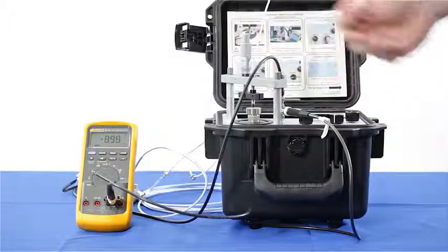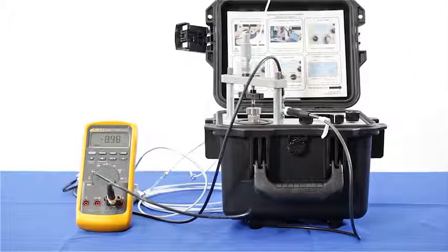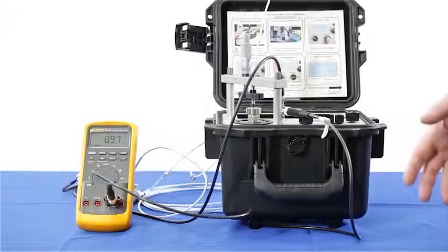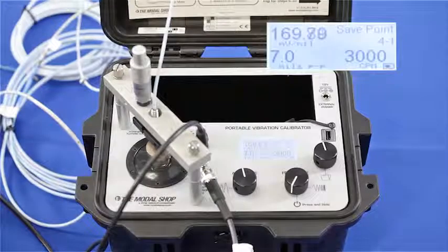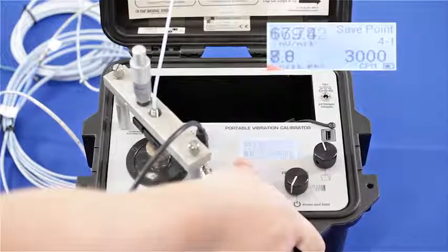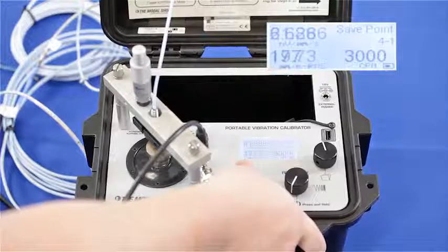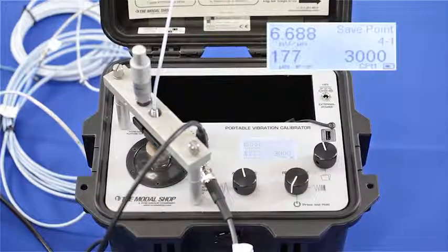So I can make my gap voltage look correct at -9 volts by moving the proximity probe, in this case, a little bit further away from the target. And that's going to cause our dynamic output to change even more. You can see now that I've corrected my gap voltage and mistakenly changed the position of the proximity probe, my output has dropped even further to 177 millivolts per mil, or in microns, an output of 6.68 millivolts per micron. Remember, my vibration protection system is expecting 200 millivolts per mil, so this is certainly going to throw my alert and alarm levels.